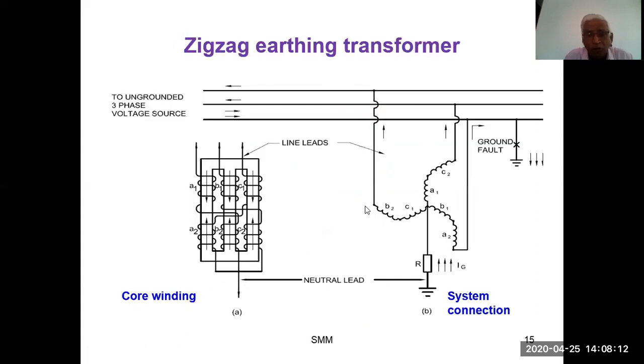Now, people who use ungrounded systems, generally people of GENCO, generating companies, use it for their internal benefit. There is nothing wrong in using it, but you should be careful. So they use a zigzag earthing transformer. You can see that the primary is connected in a zigzag connection, but a star connection, one point is earthed here. And whenever there is a fault on this, the current flows through this and it gives a signal through its secondary.